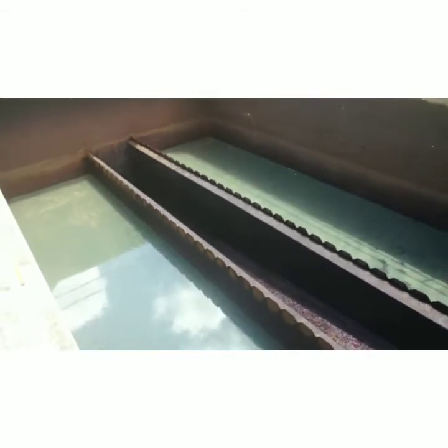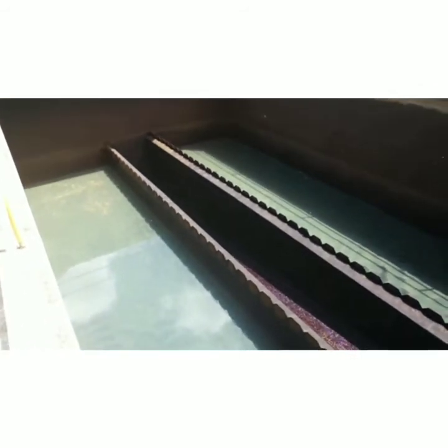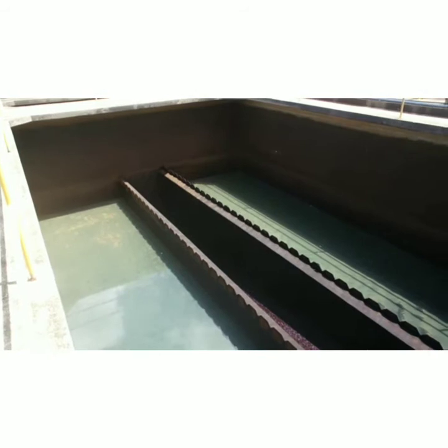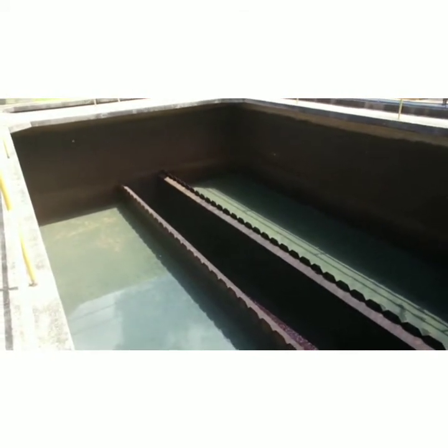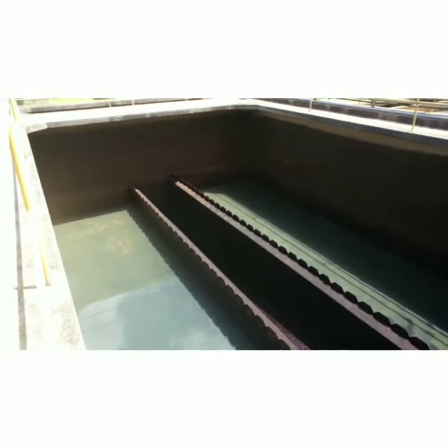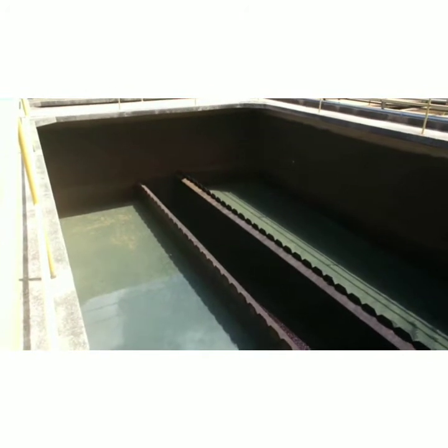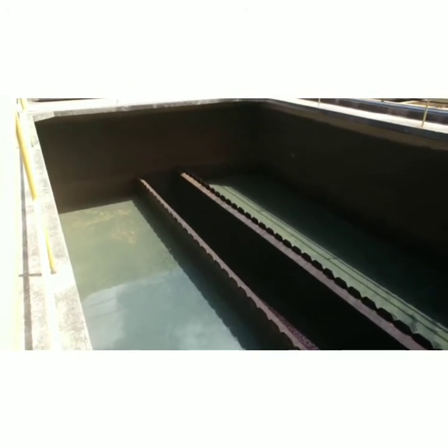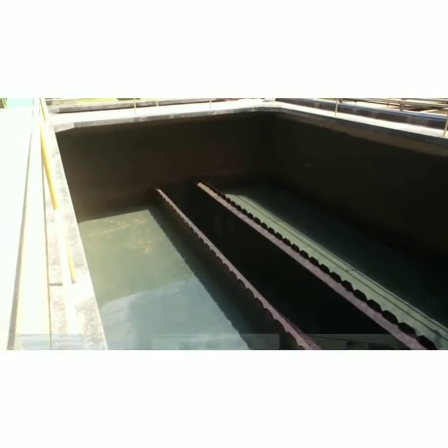From the bottom, it has a setup where the air pressure starts. It has a depth of 2.5 to 3.5 meters. At the bottom there is gravel, and when it comes to the top, it's very fine sand filters. Observe only the sand filters now with one set of water wash troughs, and I will move further.